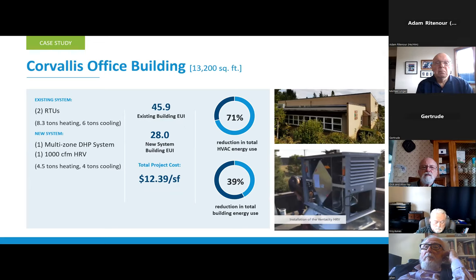Another Oregon project is a Corvallis office building. In this building, they only retrofitted about 25% of the building floor area due to project budget restraints. But still, they ended up with a 71% reduction in total HVAC energy use, and then only a 39% reduction in total building energy use. And I think that's due to them only retrofitting 25% of the building floor. And they went from two RTUs to a multi-zone ductless heat pump system and one HRV.